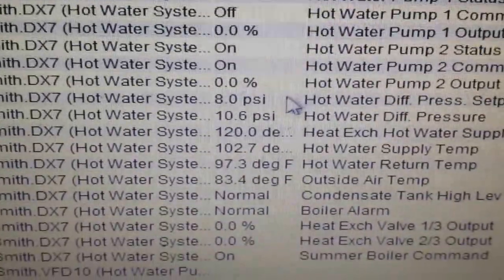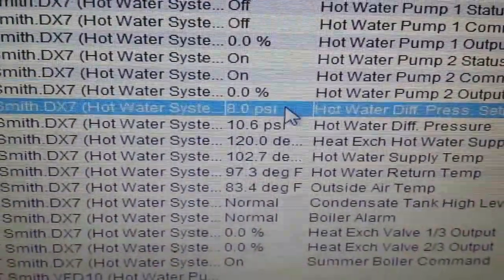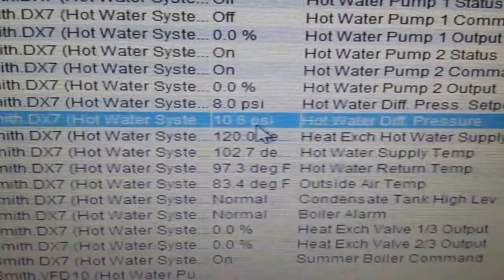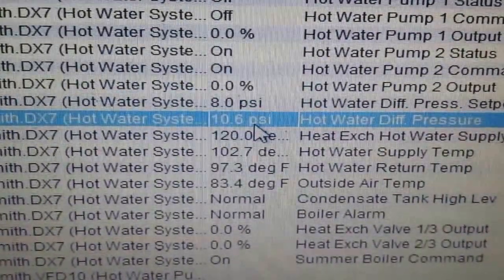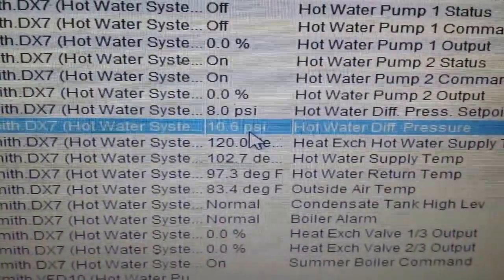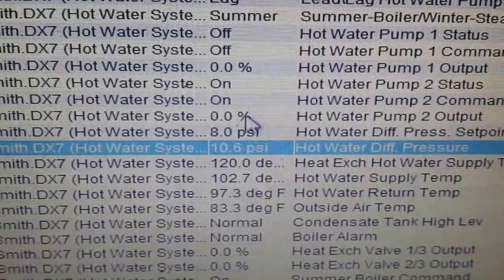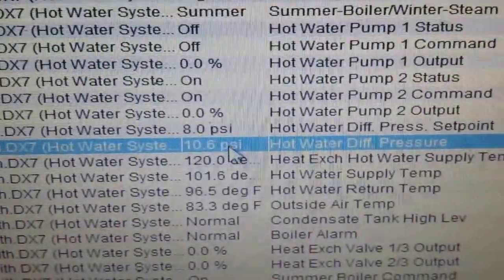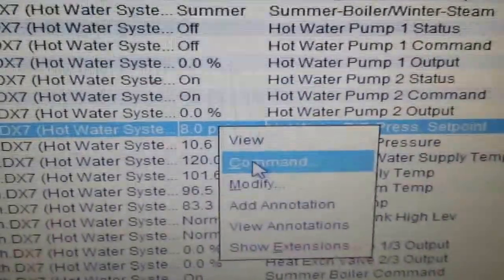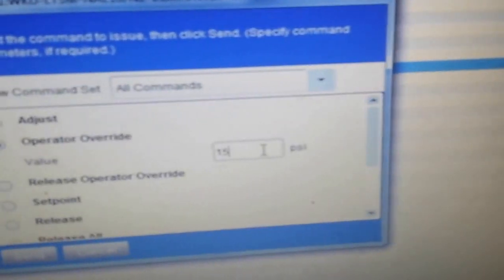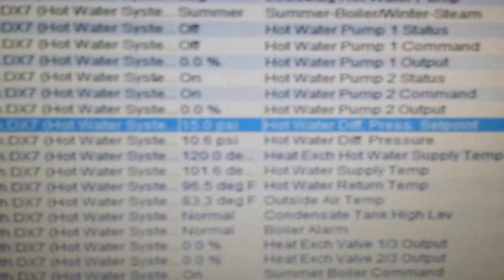You can see here that our hot water differential pressure set point is 8 PSI. The actual differential pressure measured from the sensor is 10.6 PSI. That means even at a minimum, this drive is exceeding the pressure set point — that is why our command is at zero percent. However, if I were to change this set point, you would see an increase in the command signal to the drive. I am going to raise this to 15 PSI. In a moment, the output to the drive will increase.